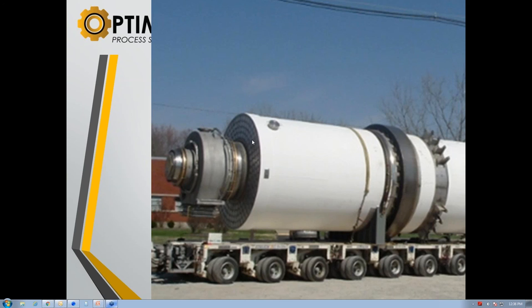Then you can reach through there and actually cut the end off that tube and collapse the ring out, and pull a single tube out. They go out from the opposite end, and then they push back through, and it can be rolled through that handhole cover there. That has a plate on the backside with a gasket. So this part is an ASME code vessel that's built for the pressure of the steam. It would be easy, on that particular unit, to block that tube off. The other unit that we showed would be a little bit more difficult. You'd have to go in and cut that tube and put a plug in it. That's a very good question.